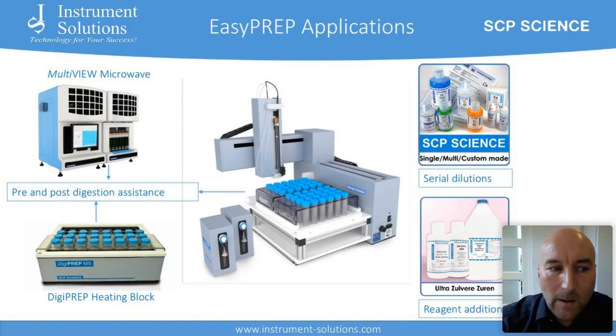To give some examples of the applications that it can be used for, I'm using some other products supplied by SCP Science. On the left side, you see the multi-view microwave system, which is a closed vessel acid digestion system, and down below the DigiPREP heating block. EasyPREP can do pre and post digestion assistance for these systems. Before digestion, it can add the concentrated acids and any other reagents. After digestion, it can add internal standard, normalize, then do homogenization with the bubble stirrer, and after that transfer to an autosampler tube, or dilute and transfer to an autosampler tube. It can also be used for all other types of liquid addition and reagent addition, and also for making serial dilutions for standards or making multi-element standards.